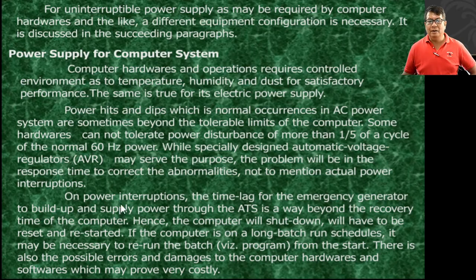So, on power interruptions, the time lag for the emergency generator to build up, which takes a few minutes, and supply power through the ATS is way beyond the recovery time of the computer. So, it is difficult, it is not direct. The computer will shut down and have to be reset and restarted.